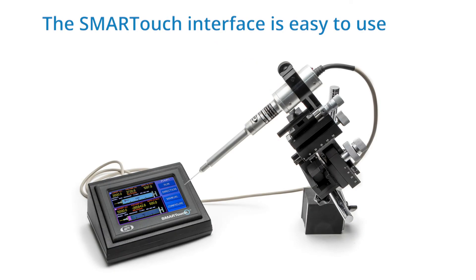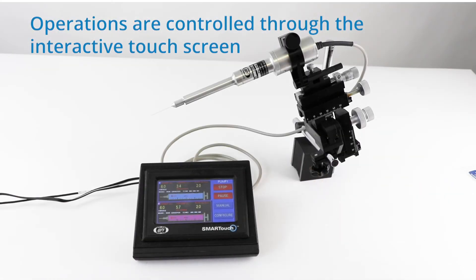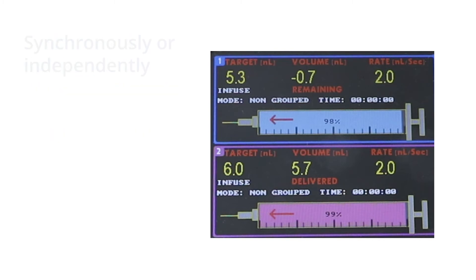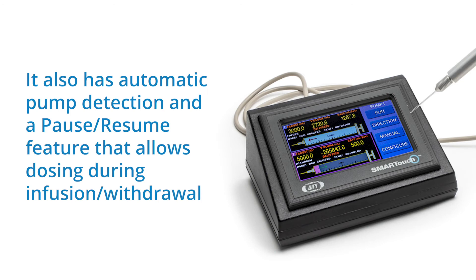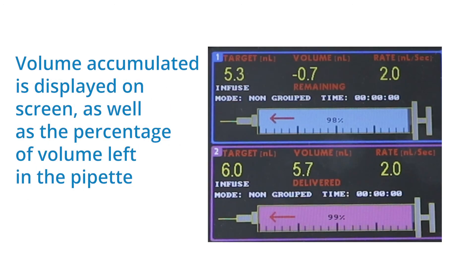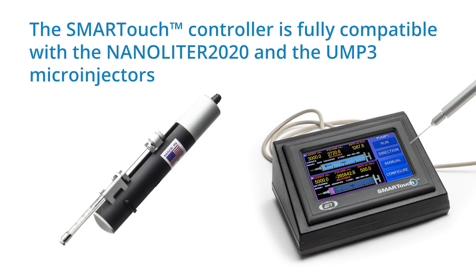Third, the SMARTouch interface is easy to use. All operations are controlled through the interactive touch screen. The controller display offers a graphical representation of the volume status. With its dual display, you can easily control two pumps simultaneously, either synchronously or independently. It also has automatic pump detection and a pause-resume feature that allows for dosing during infusions or withdrawals. The volume accumulated is displayed on the screen as well as the percentage of volume left in the pipette. The SMARTouch controller is fully compatible with the Nanoliter 2020 and the UMP3 microinjectors.